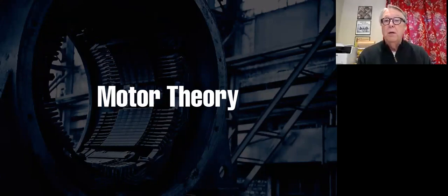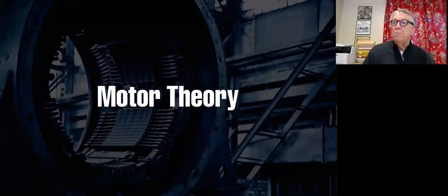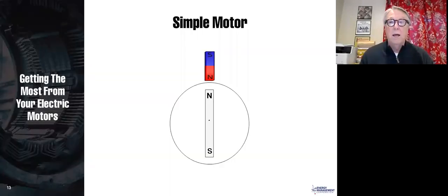You probably know that the biggest cause of motor failure is motor bearings, and the biggest cause of failure of motor bearings is improper lubrication. And so it's a very, very important subject. And who is it that lubricates the bearings? Well, my answer is generally the new guy, because it's not the fun job. And the new guy also tends to be the least knowledgeable. And that can be a disaster for your facility if those bearings aren't being lubricated correctly.